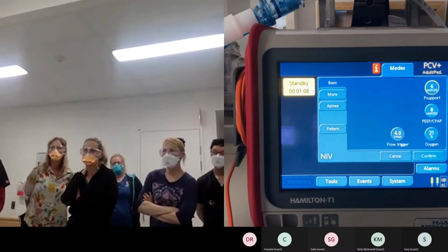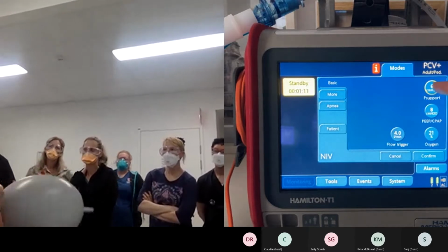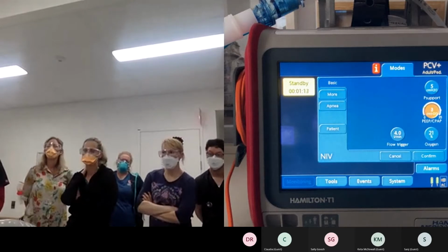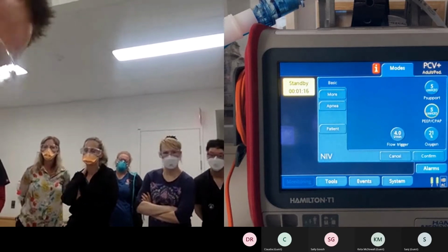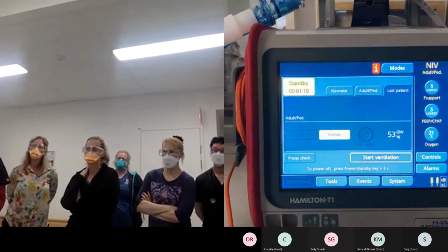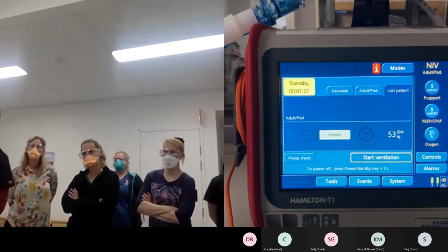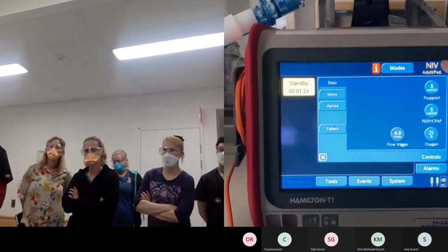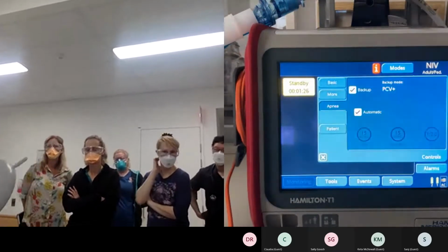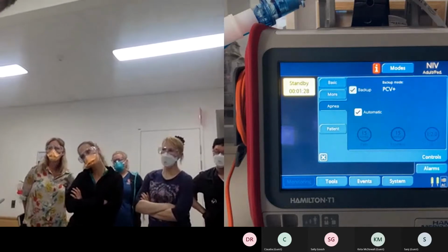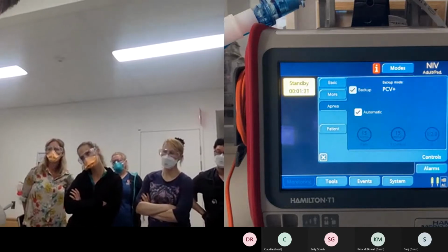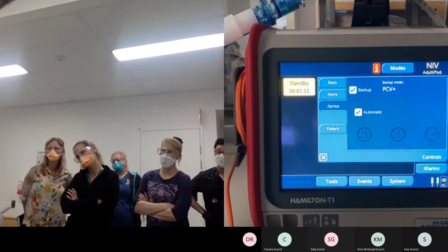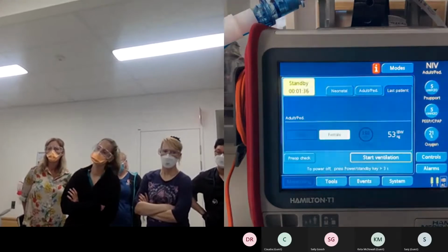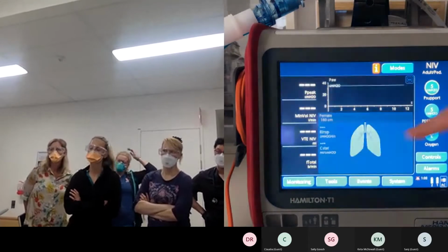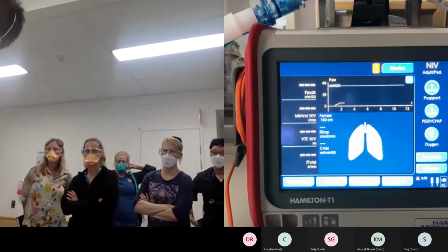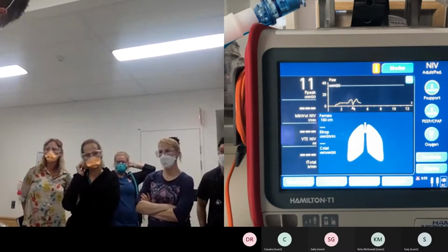Just for the guys, we have it set on 5 and 5, so that's the equivalent to when you usually say BiPAP 10 on 5. Yep. And you've got 5 and 5, so that'd be 10 on 5. Yep. So in the NIV mode, you've also got apnea backup. If your patient becomes apneic, the ventilator alerts and lets you know that it's gone into apnea ventilation. I'll show that to you, and I'll show then how that differs to NIV ST. So here we go.